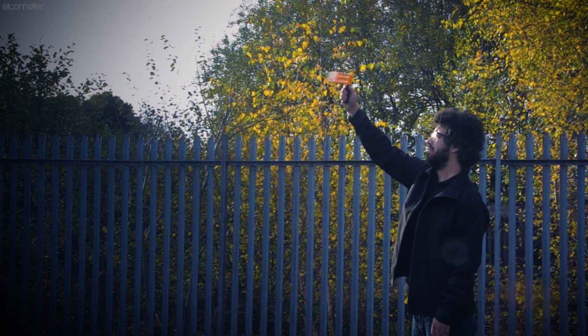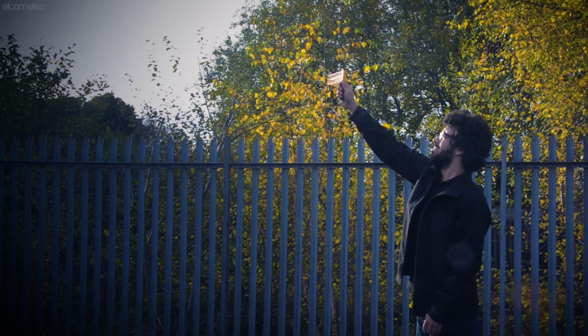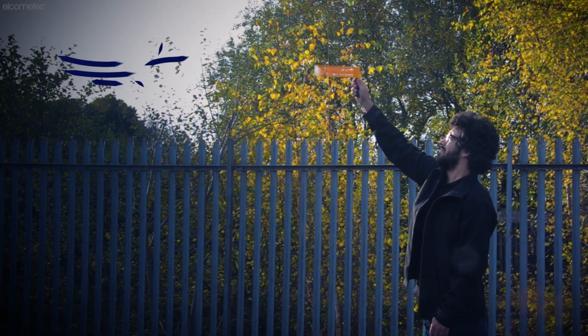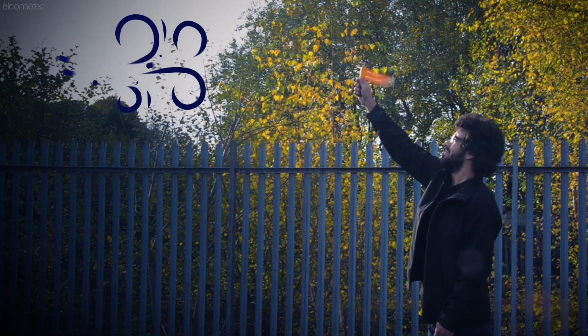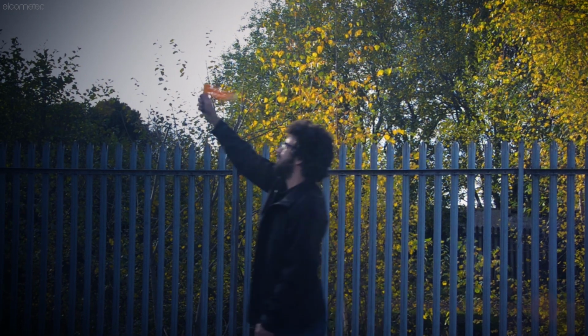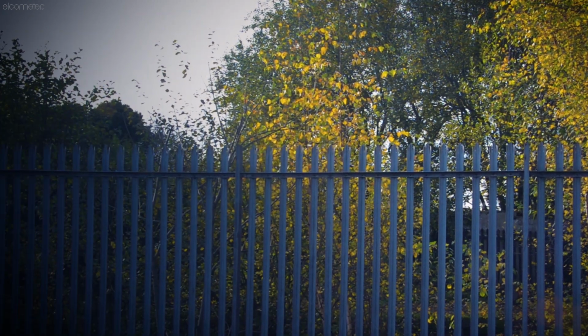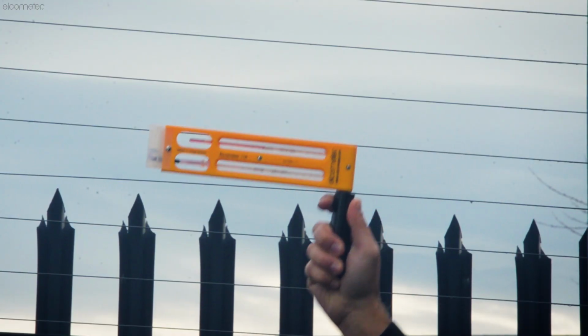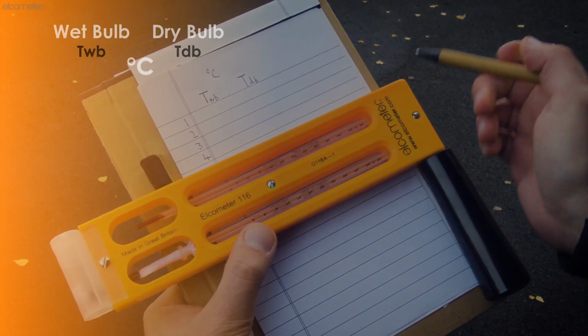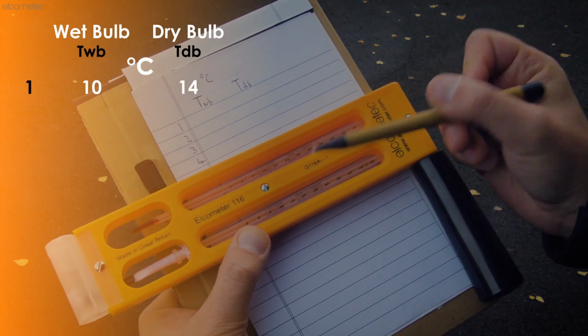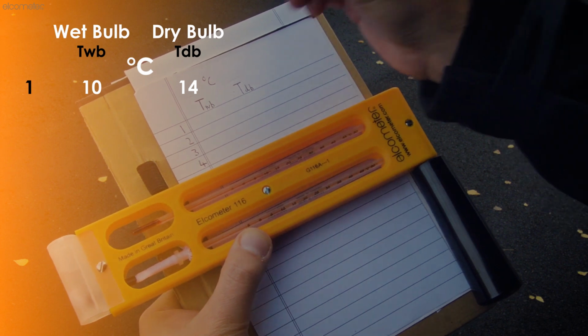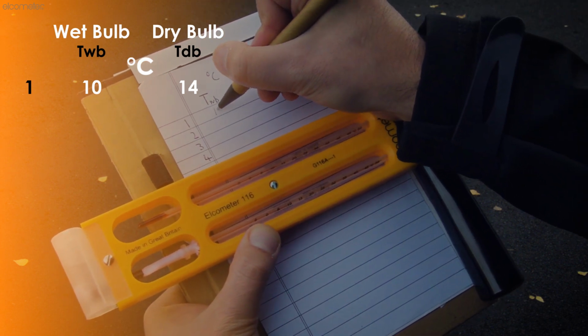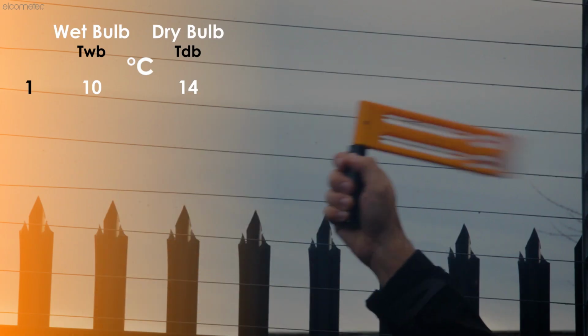When whirling the hygrometer, to reduce the effects of your own body temperature, hold the hygrometer in front of you, facing the wind. On a still day, we recommend slowly walking forwards whilst whirling. After the 20 to 40 second whirl, the thermometers are quickly read, noted, and then the hygrometer is spun again. After another 20 to 40 seconds, once again read the thermometers.